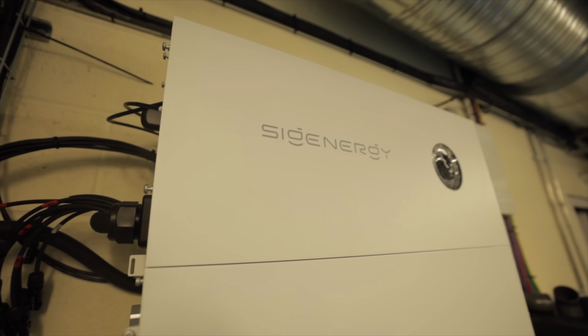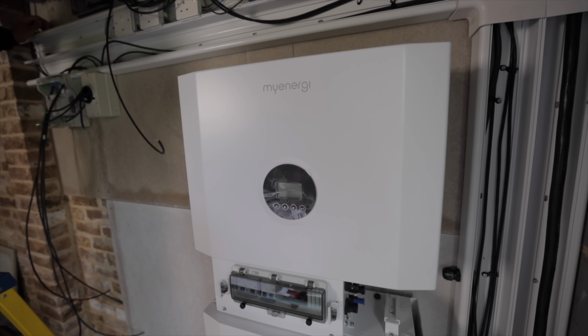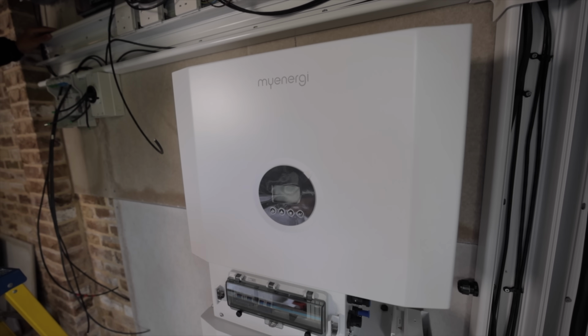That inverter is going to be the limiting factor in terms of how fast you can charge the batteries up, but also how fast they can discharge. In other words, how much power they can output during a grid outage. What you may need to do in a backup situation is turn off some heavy appliances. For example, imagine that you're running the oven and the kettle and the washing machine. That can easily rack up to 7, 8, 10 kilowatts of power being consumed at any given time. And if you've only got a 6 kilowatt inverter, that's going to trip out the system and you're going to lose all power. So what you might want to do is turn off a couple of appliances, and then the inverter should kick in and start to give you power again.